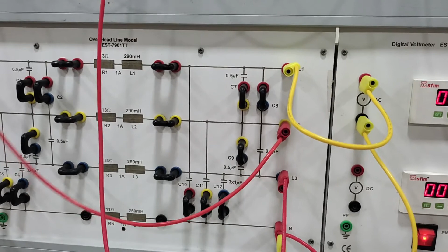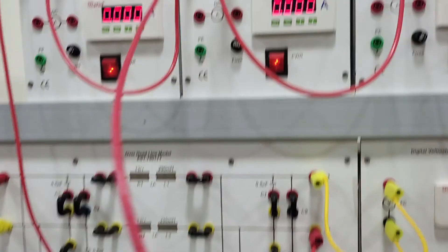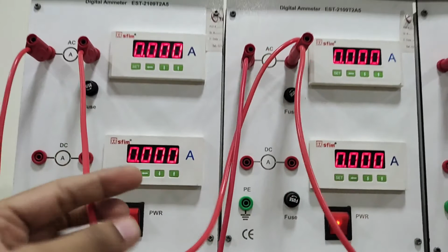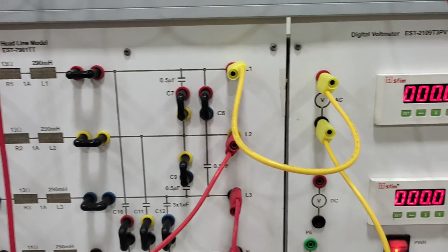So in order to measure the short circuit current for L2, the output of L2 goes towards the first ammeter, and in order to measure the short circuit current for L3, the output of L3 goes towards the second ammeter, and in order to measure the earth current, the output goes towards the third ammeter, and the remaining points of the ammeters are common. Here you can see all these points are common, as we have previously discussed in our manual. So these ammeters are connected in series with the two phases and the neutral, and then these are short circuited together, and this L1 phase is the healthy phase because it is not short circuited.